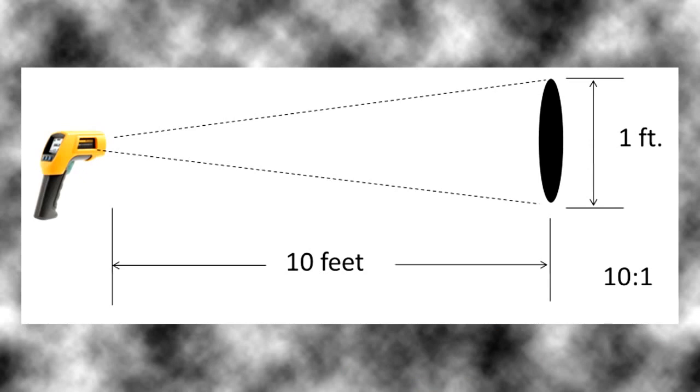Distance to spot ratio is used to express the ability of an infrared thermometer to measure temperature of a surface from a distance. The D to S ratio is the ratio of the distance from the IR tool that you're using to the surface that you're measuring.